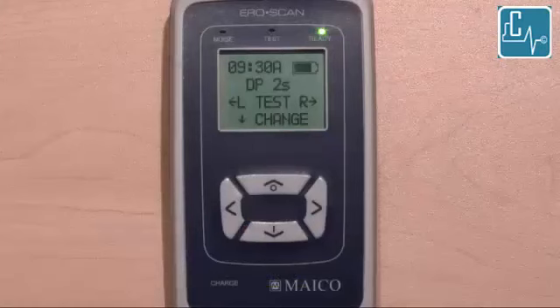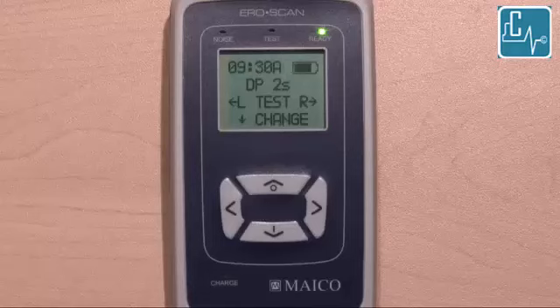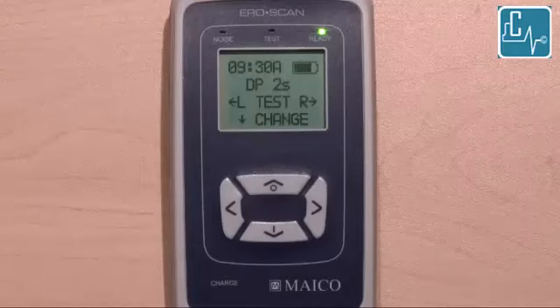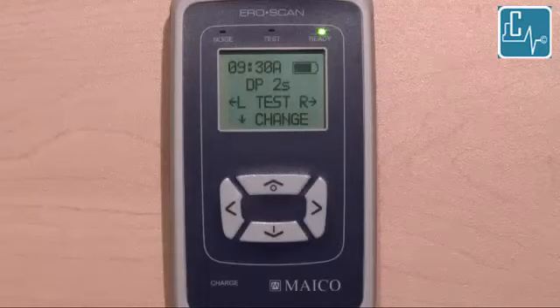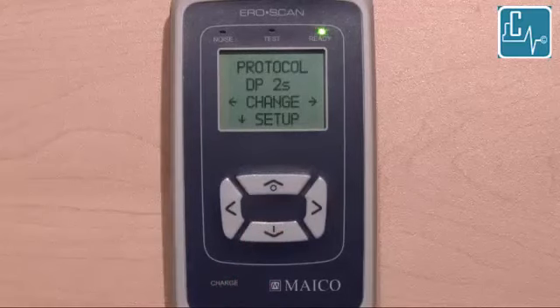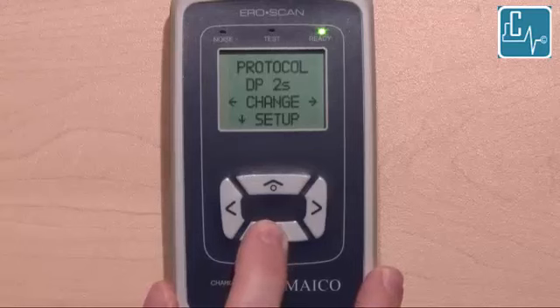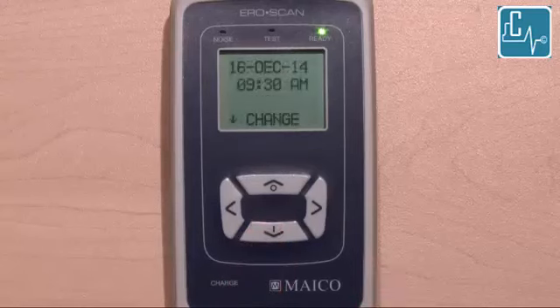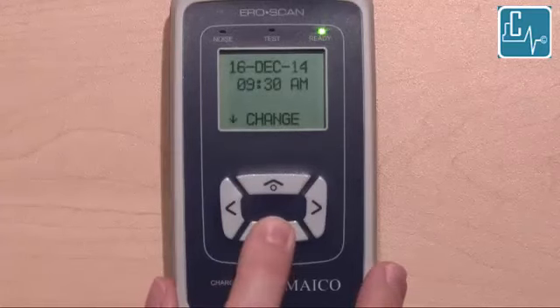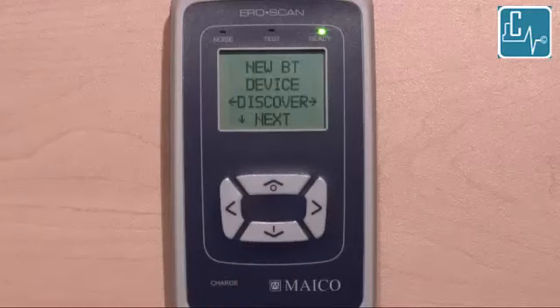Patient names can be loaded into the ERO SCAN device before testing to make saving several patients quick and easy. If using patient names in the device, you will need to set the device to store 250 tests in the Setup menu. Press the down Change arrow from the main test screen. Press the down Setup arrow. When change is displayed with the date and time, press and hold the down arrow key for 3 seconds until the green ready light at the top of the device goes out.